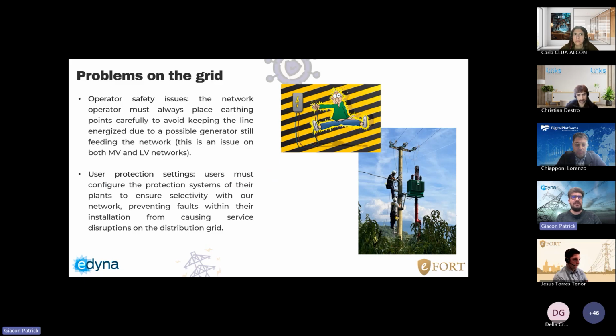Operator safety is also a critical aspect. Network operators must always place earthing points very carefully to avoid keeping a line energized by a generator that is still feeding the network. These risks exist on the medium and also on the low voltage network, and require strict operational procedures. In addition, user protection settings play a fundamental role. Users must correctly configure the protection system on their plants to ensure selectivity with our grid. This is essential to prevent a fault on the user grid from causing outages on the distribution grid, also on the Edyna grid.